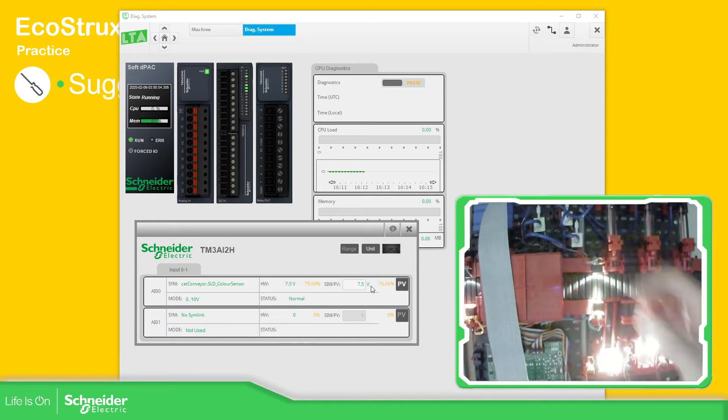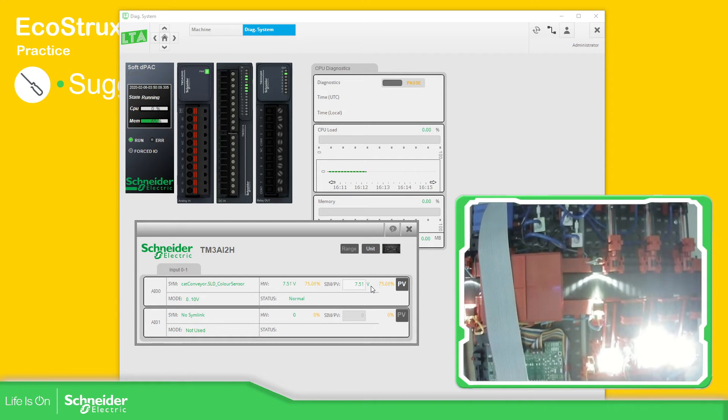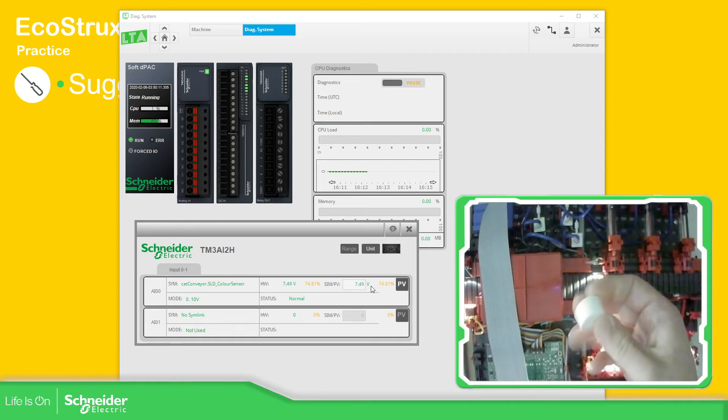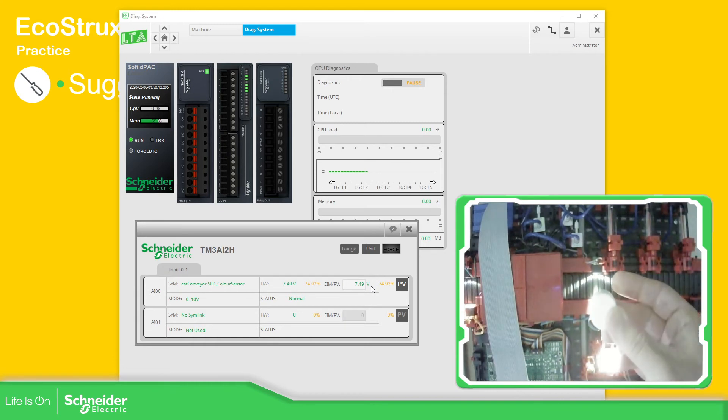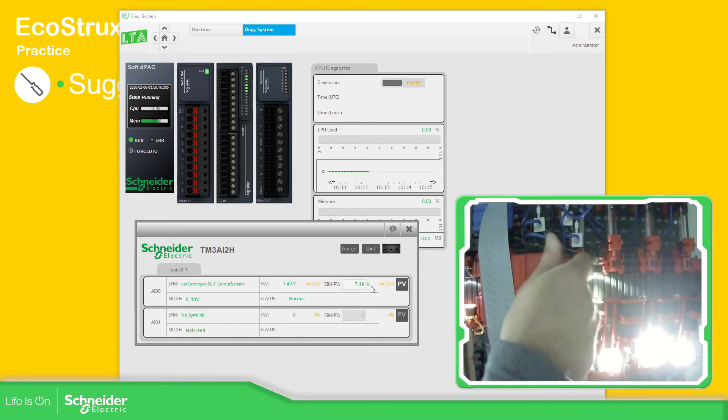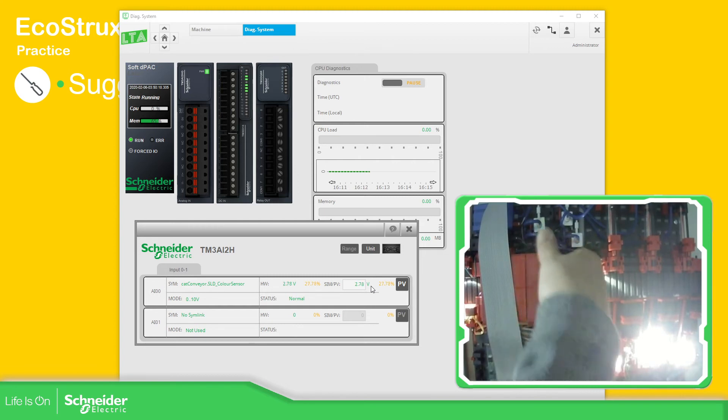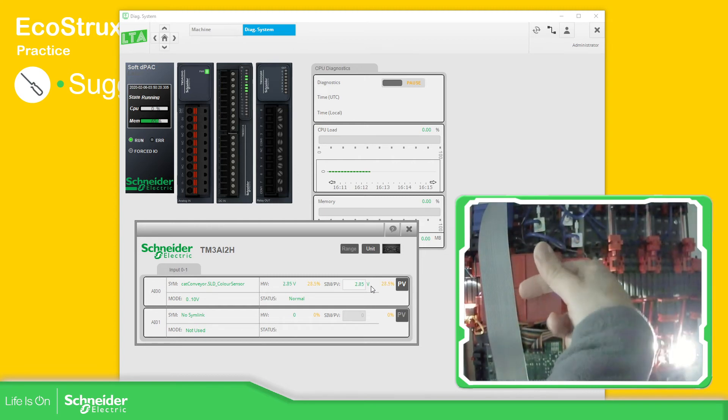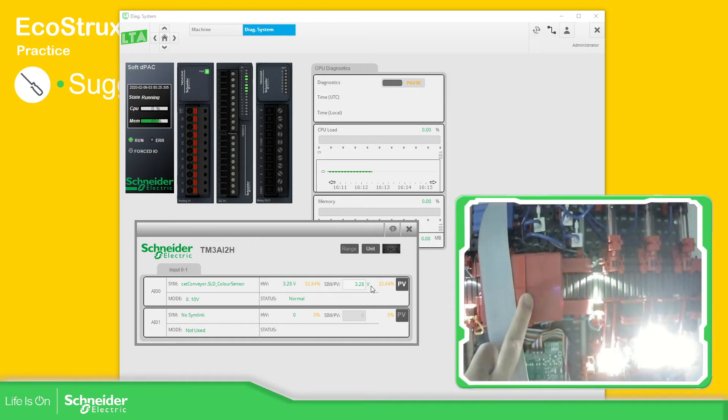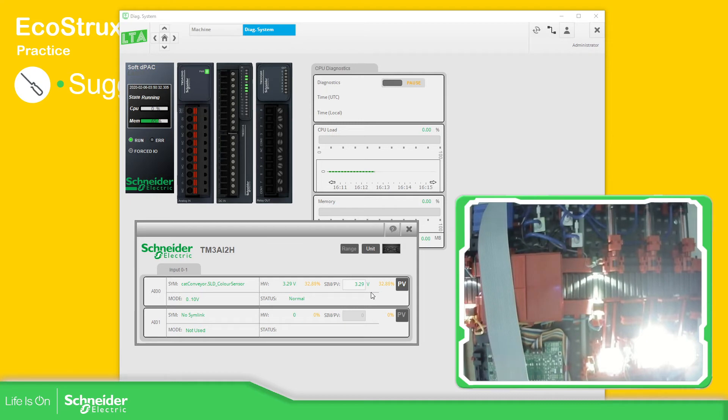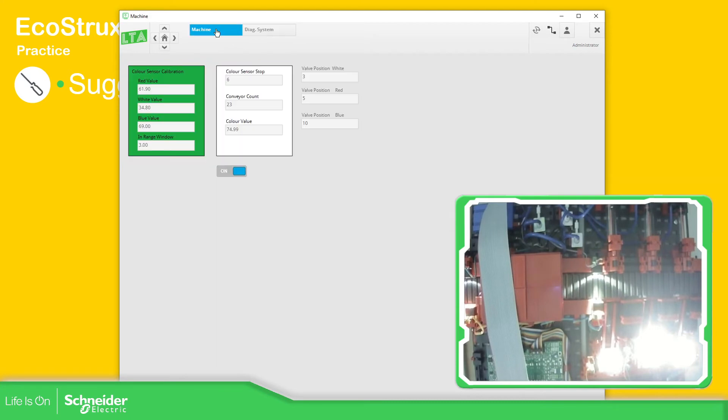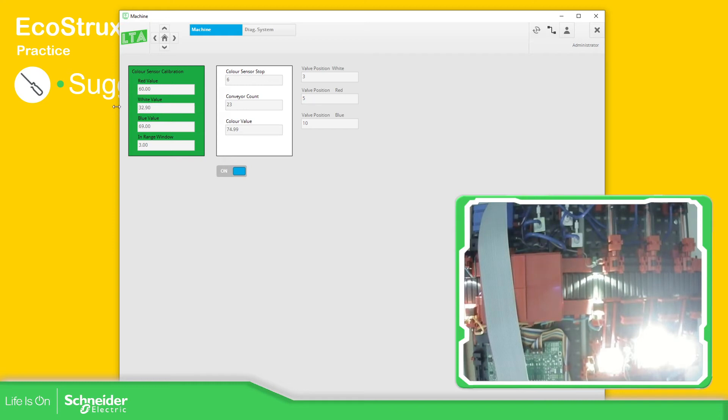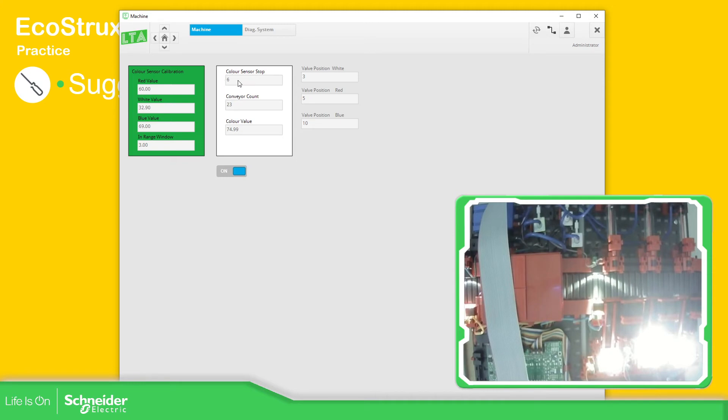I'm going to put the white over here. There we go, so I have the white in here. We can detect - as you can see I got 32.9. So as soon as we have these values, we can introduce them here. This one gives me 60.0, the white gives me 32.9, and the blue 68.5. Let's leave it in there. This is what I have for the calibration sensor. Now let's go for the stopping - I already have this value which is 6, and then this is for testing.